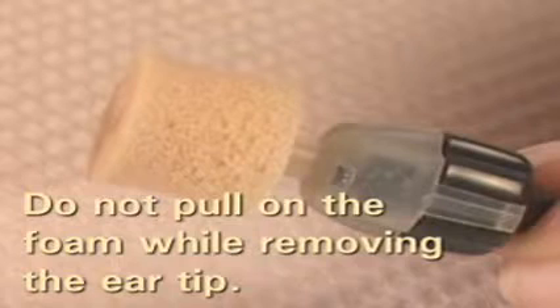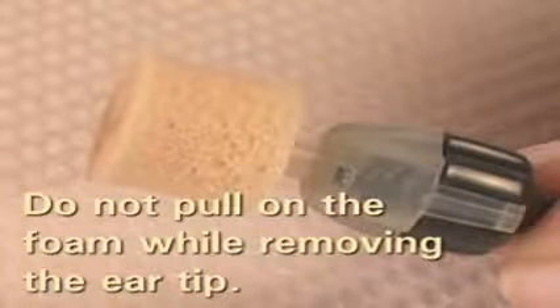To remove foam tips from the nozzle, hold the probe body with your fingers on top of the nozzle clips. Then, with the other hand, place your fingernails behind the clear tube at the base of the nozzle and slide the tube toward the end. Do not pull on the foam. This will cause suction in the tube around grooves in the nozzle and will actually impede the removal.